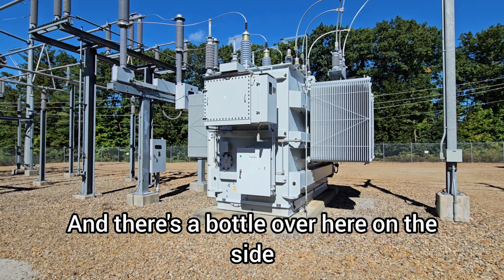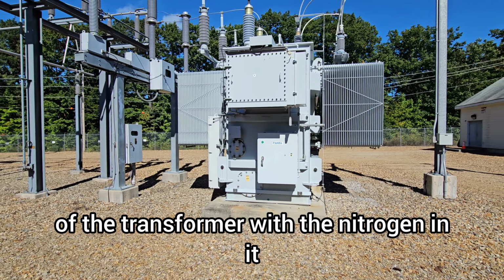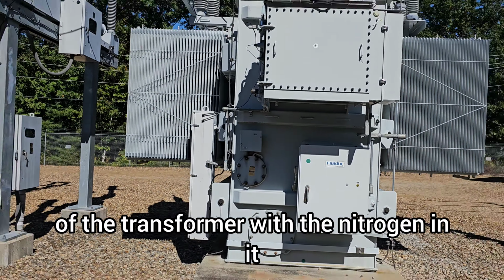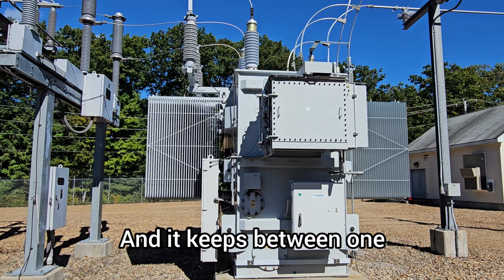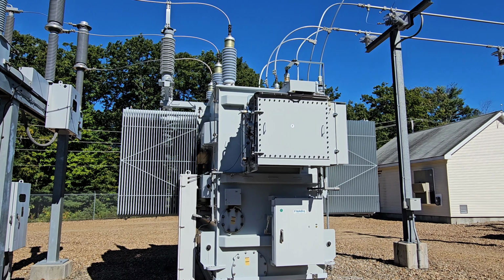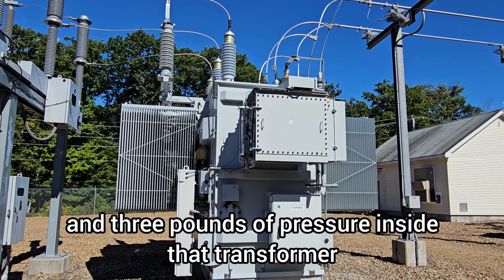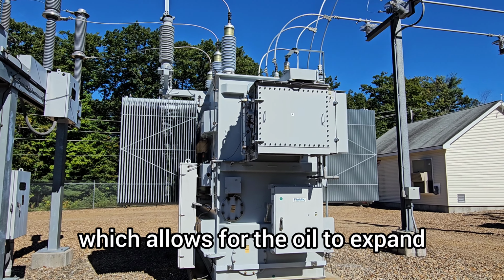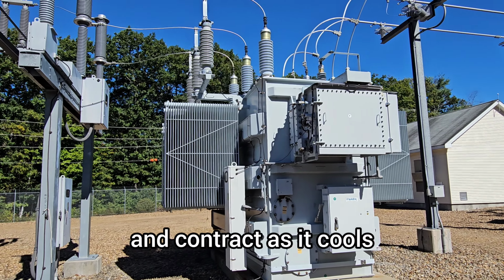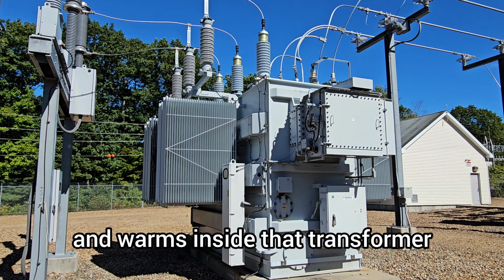There's a bottle on the side of the transformer with nitrogen in it, and it keeps between 1 and 3 pounds of pressure inside that transformer, which allows for the oil to expand and contract as it cools and warms inside.